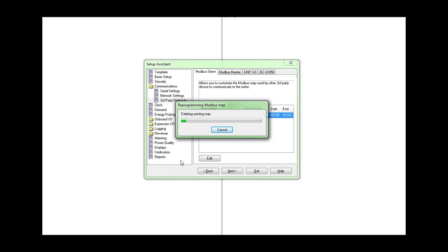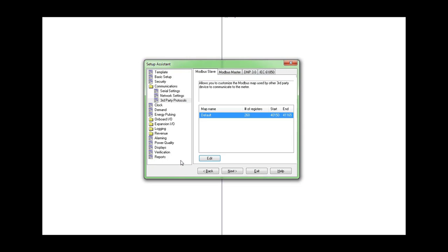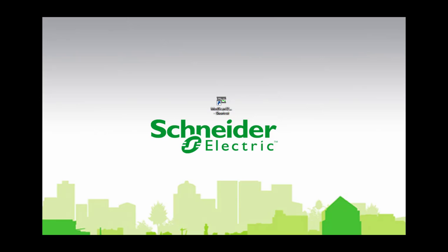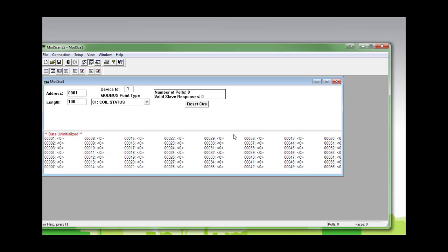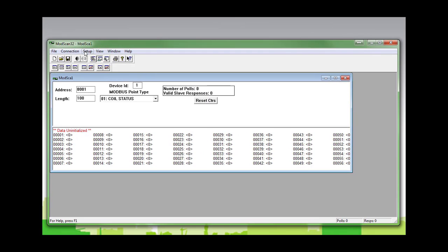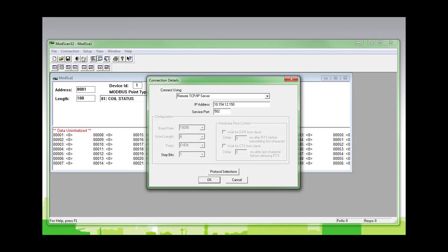At this moment, the Modbus map is being reprogrammed. First of all, the old one is deleted, and then the new one is downloaded to the meter. So we can say that the Modbus map is now updated. But how can we be sure of that? I will use a Modbus tester, a Modbus reader like Modbus Scan, and connect to the meter in order to check that the new Modbus addresses are readable and that we can see real-time values.